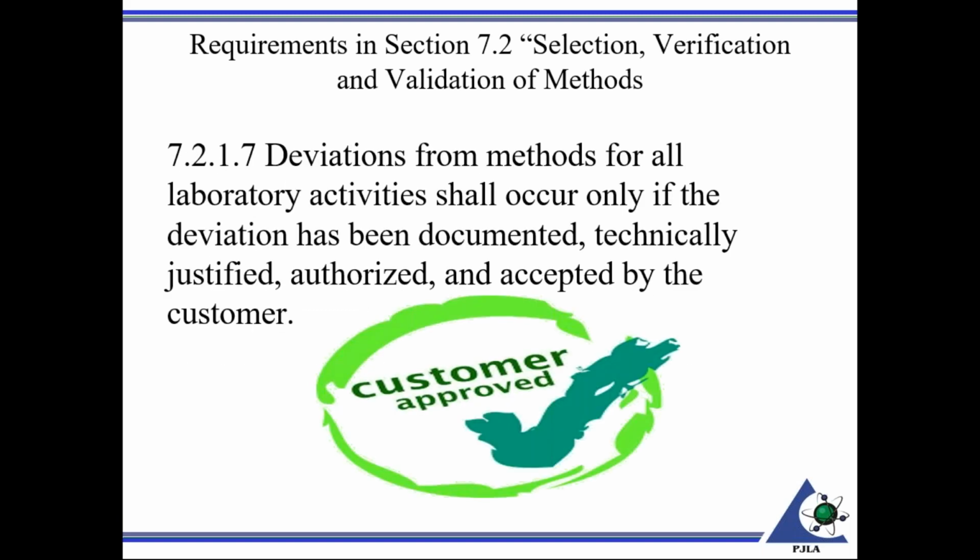7.2.1.7, of course, you're expected to follow the method. Any deviation from the method for all laboratory activities shall occur only if the deviation has been documented, technically justified, authorized, and last but not least, it has to be accepted by the customer.